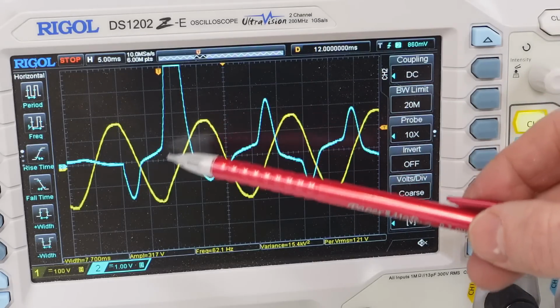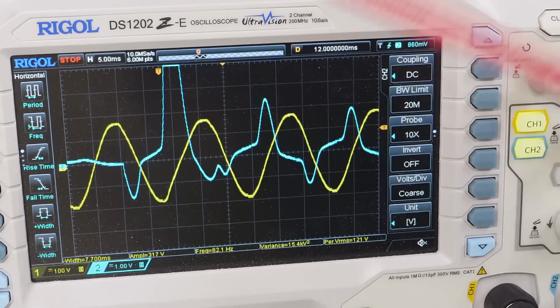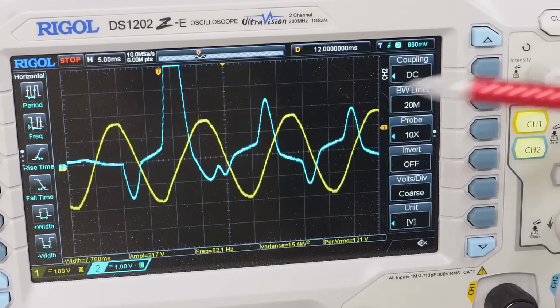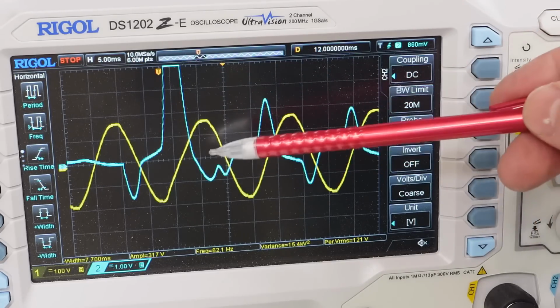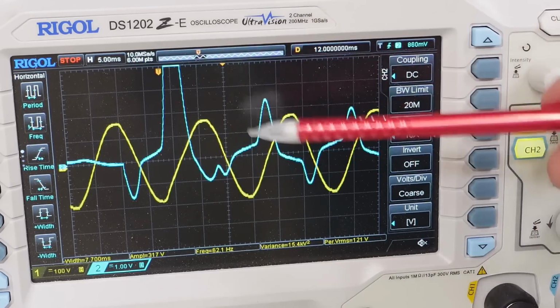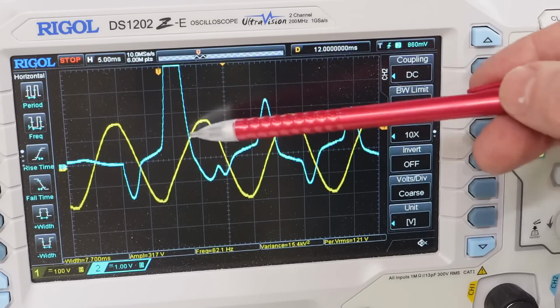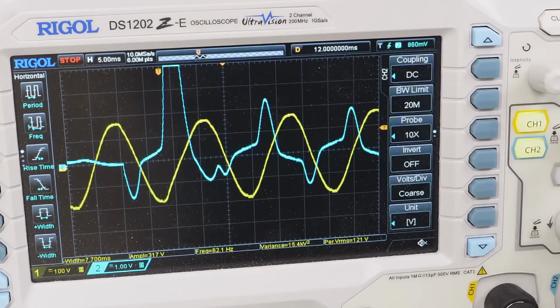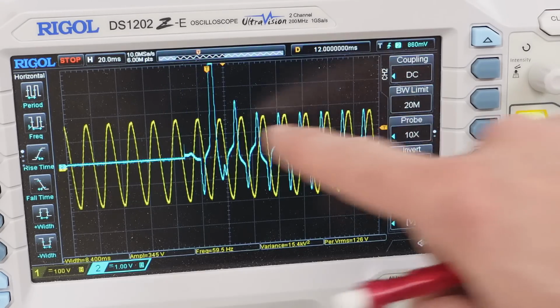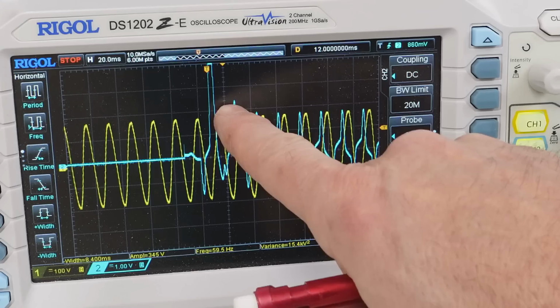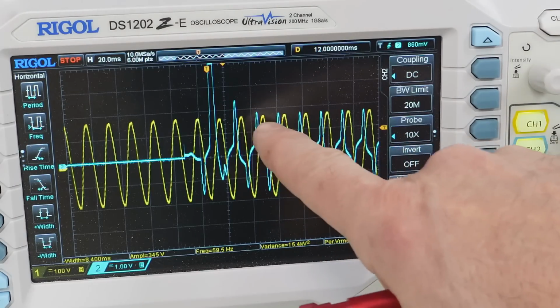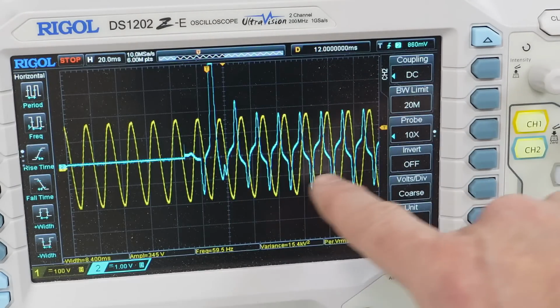That's what happened here. We get this huge spike in current because we're trying to drive more flux into the core than it can take, and since it's not taking any more flux, there's less induced voltage to take it away, so all of it goes through resistance. As a result, it balances itself fairly quickly. The current spikes a little higher here and here, but after about 2 cycles it's actually balanced itself. I don't think that was even worst case.